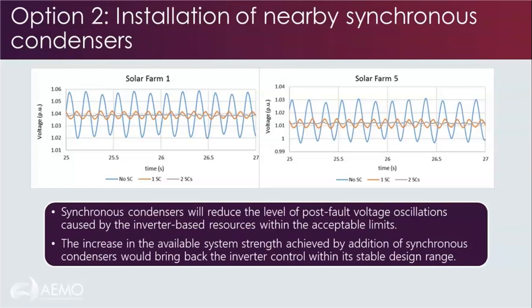Again, we can see here that as soon as the first synchronous condenser is introduced, the level of oscillation reduces substantially. And having the second one further suppresses the oscillations to the level that we consider acceptable as per the standards that we and the network owners need to operate against. The underlying reason for this improvement is that a synchronous condenser increases the level of system strength available to the inverter-based resource, such that a stable outcome can be achieved without making any changes to the original design or control tuning of the inverter-based resource.